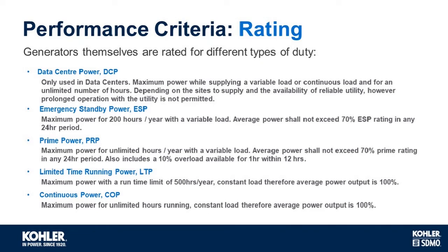LTP, or limited time power, that's the maximum power with a runtime limit of 500 hours, but now it allows for 100% constant load. And finally, continuous power, or COP. Now that's a maximum power for an unlimited number of hours, and again at a constant load, at 100%. Please note that COP is not normally used in mains to standby applications.